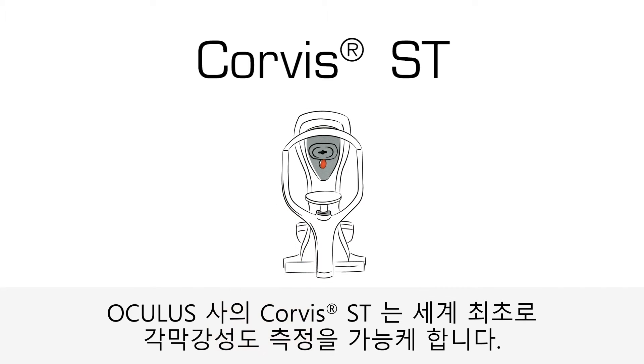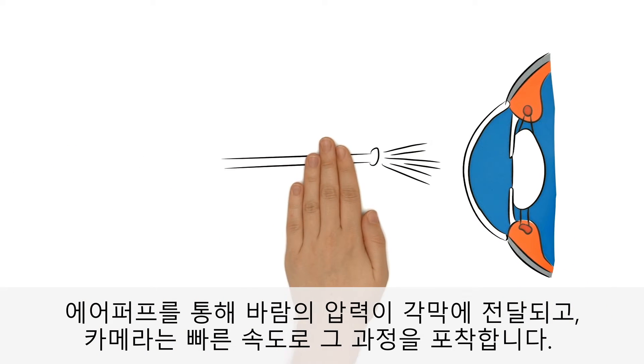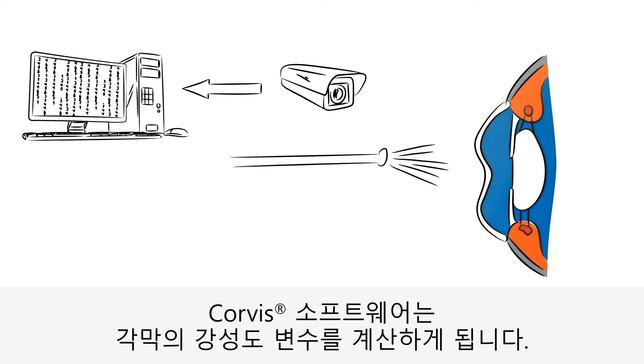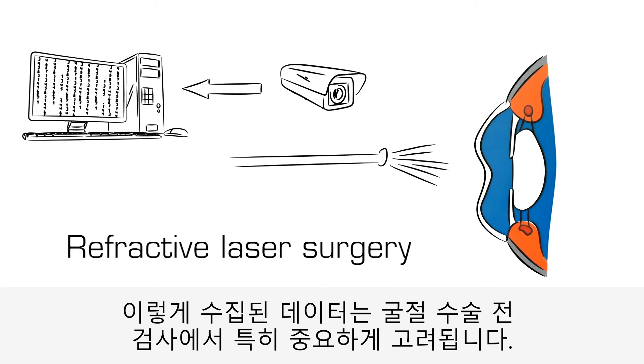Corvis ST from Oculus makes this possible for the first time ever. Pressure is applied to the cornea via an air puff, and a high-speed camera records the change. The Corvis software uses this to calculate a stiffness parameter of the cornea. These data are of particular relevance for screening before refractive laser surgery.